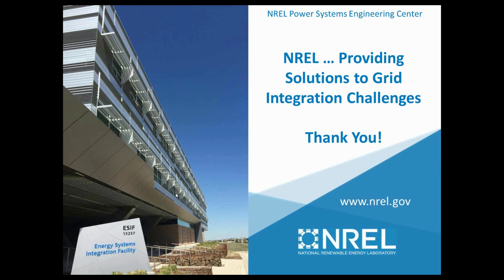Okay, well, this is a good question. It gets asked all the time. There's general guidance for this in IEEE 1547.2, which is the application guide for 1547. It talks about grid stiffness and when you can determine that. At some level you can say a really stiff grid has a short circuit ratio of, I think it's 25, if that number sticks in my head. That doesn't necessarily mean you have a weak grid at something less than that, but you probably have to evaluate it more closely.